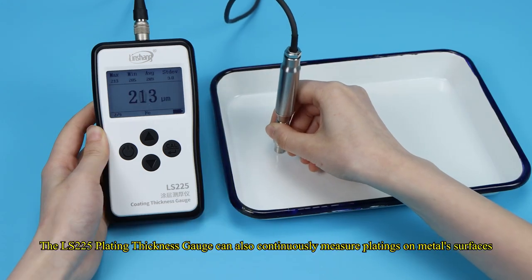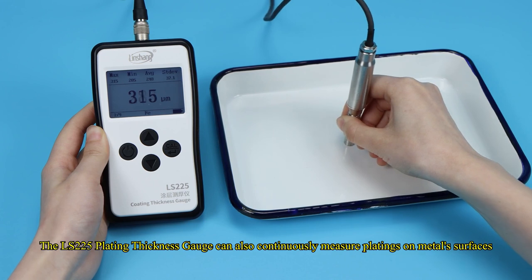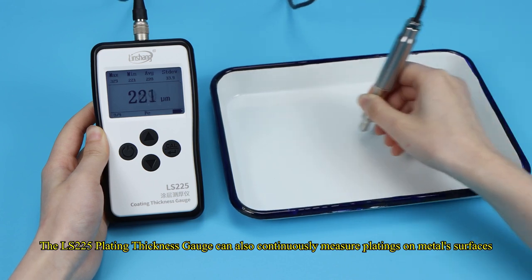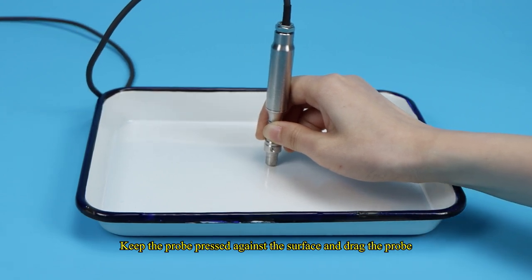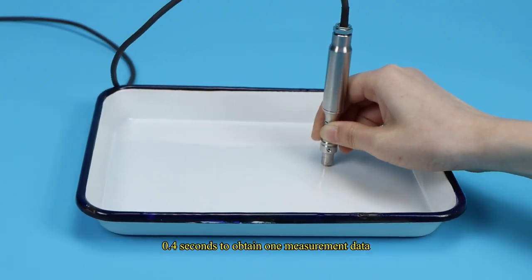The LS-225 plating thickness gauge can also continuously measure platings on metal surfaces. Keep the probe pressed against the surface and drag the probe. 0.4 seconds to obtain one measurement data.